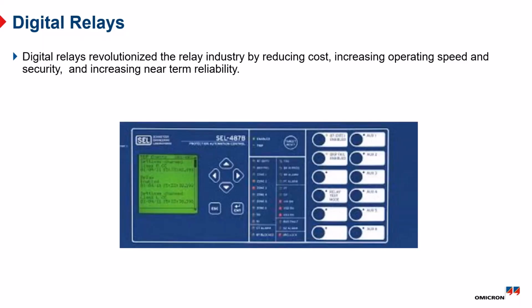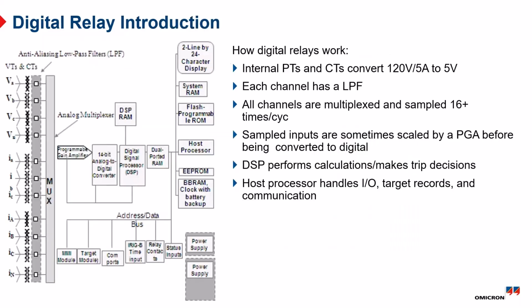Notice I said near-term reliability because, with the electromechanical relays, it wasn't unusual for me to go out in the field back in the day and see a relay that had been in service for 50 years. I don't think anybody thinks that you can put an SEL whatever in anywhere and expect it to last for 50 years. It's probably not going to do it for just electrolytic capacitor life alone. But back in the day, that was certainly more the norm.